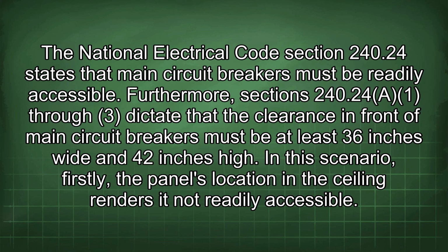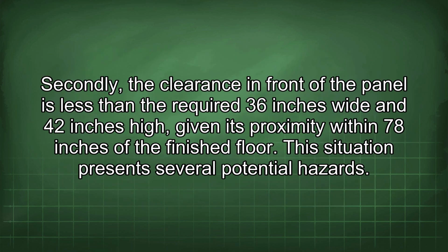In this scenario, firstly, the panel's location in the ceiling renders it not readily accessible. Secondly, the clearance in front of the panel is less than the required 36 inches wide and 42 inches high, given its proximity within 78 inches of the finished floor. This situation presents several potential hazards.